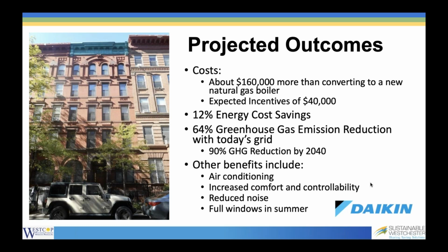This building currently has an oil-fired steam boiler, so they'll no longer have that on-site combustion when they bring in air source heat pumps. It's a 10-unit housing development fund corporation co-op, a typical pre-war walk-up apartment building, with tankless hot water coils for domestic hot water, and the boiler is nearing the end of life but still functional. Bringing in the air source heat pump system at this time helps with the return on investment.